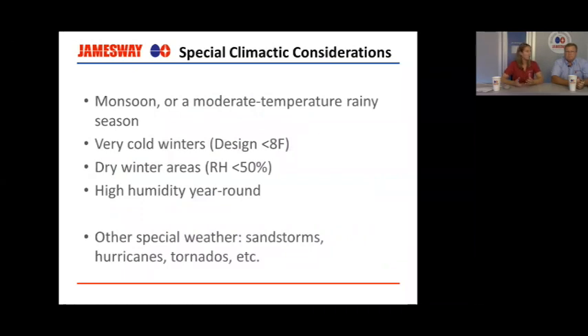And then what about special climate considerations? So like we talked about, monsoon, a moderate rainy season, very important. Other concerns are very cold winters, like we said, for freeze up, for things like that. Dry winter areas, that would be the prairies in Canada, where your relative humidity is very, very low during the winter, and also you're using a lot of heating, so your rooms are going to be very dry. In those areas, it's absolutely essential to have humidification in your room so that you can get up to that 45% target that we have for platinums. And then areas that have high humidity year-round. If you are heating and still need dehumidification, that's another consideration. And then other special weather. Do you have sandstorms, so you need sand protection? Are there hurricanes? Are there tornadoes? Things like that.